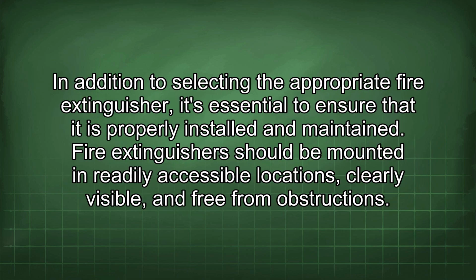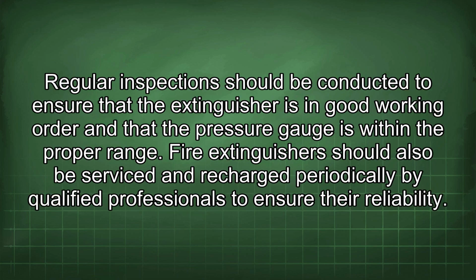In addition to selecting the appropriate fire extinguisher, it's essential to ensure that it is properly installed and maintained. Fire extinguishers should be mounted in readily accessible locations, clearly visible, and free from obstructions. Regular inspections should be conducted to ensure that the extinguisher is in good working order and that the pressure gauge is within the proper range. Fire extinguishers should also be serviced and recharged periodically by qualified professionals to ensure their reliability.